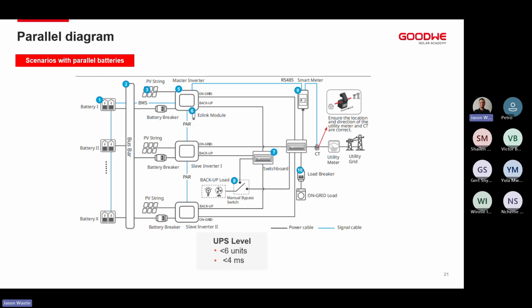When we parallel the system, we just need to make sure all the inverters have got the same operating firmware on all of them, and then we can connect them all together in parallel. We connect to that EasyLink module, which automatically creates the master inverter, and all the rest will become slaves. We can connect up to 6 units in parallel. All of them need to be the same capacity. So if it is a 6 kilowatt unit, all of them need to be 6 kilowatt units. If it's a 10, all of them need to be 10s. And we have got a switching time of 4 milliseconds, but it gives us our UPS level switching.